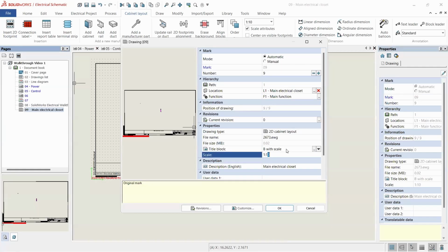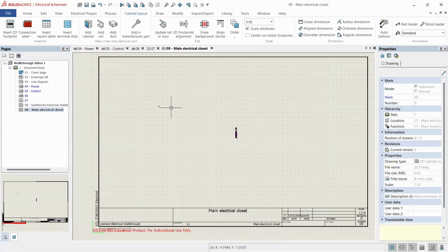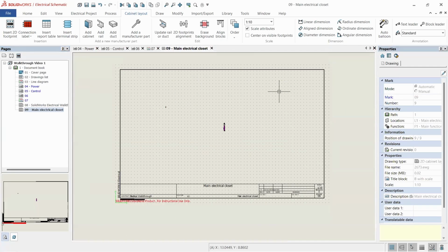Need to play with the scale because again, we're dealing with 11 by 17 paper, and most commonly in my world I deal with like 24-inch cabinets. So you need to play with the scale just to get it to look right. I do recommend with a cabinet layout, and I'll mention this again in future videos, doing the layout as you see it, sort of vertically. However, with a rectangular cabinet, it can be made bigger doing it sideways. Do the layout vertically and then rotate it and scale it up. That works out, in my experience, much better than trying to lay it out sideways.